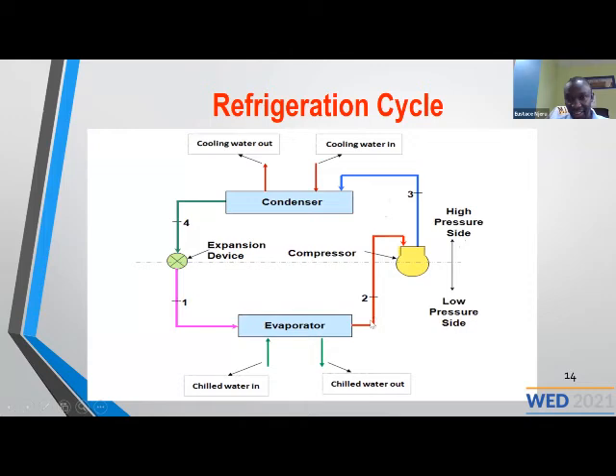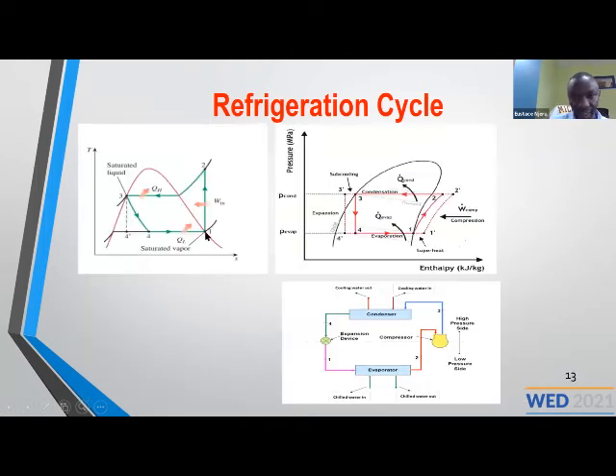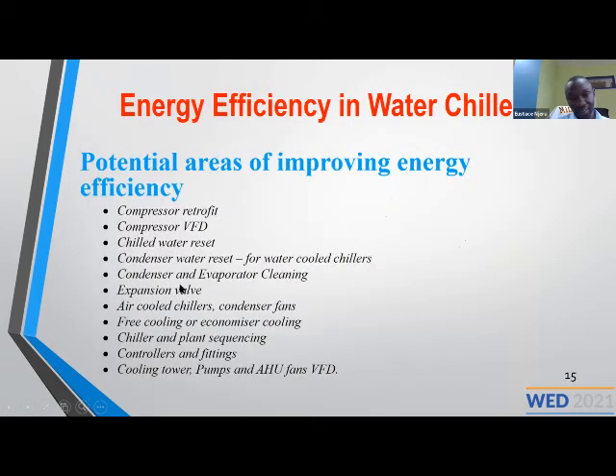And that is checked by checking what we call the superheat. If you look at this point after you have cooled your water, the refrigerant gains some heat, and before you compress it, you need to make sure that it's in vapor form to avoid destroying the compressor, because the compressor will get destroyed if you compress it in liquid form. So you need to superheat it a bit. So the work of the expansion valve as a system is a detector. So you need to use a modern expansion valve. Instead of using a thermostatic valve, we use what we call an electronic expansion valve, which is controlled by a servo motor.